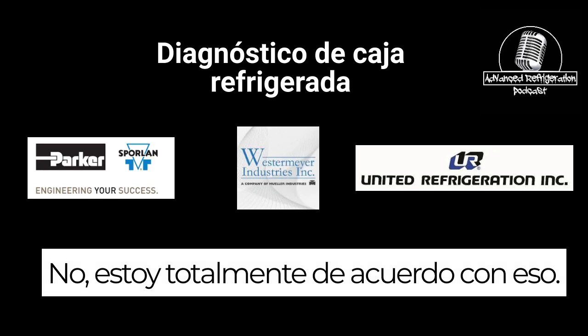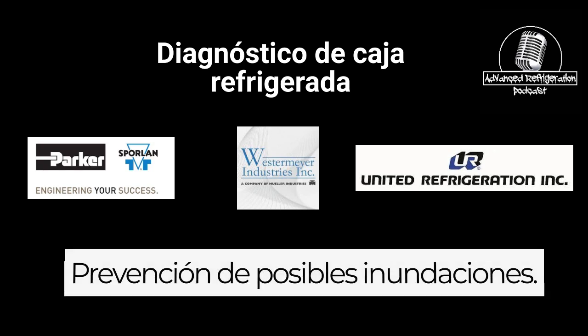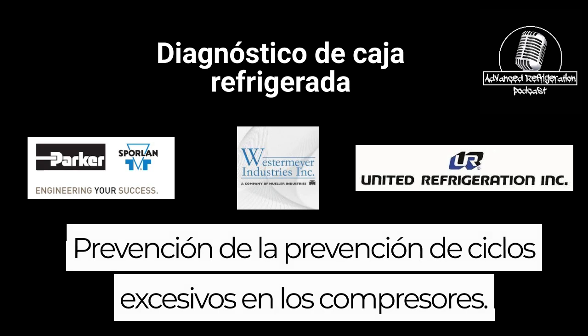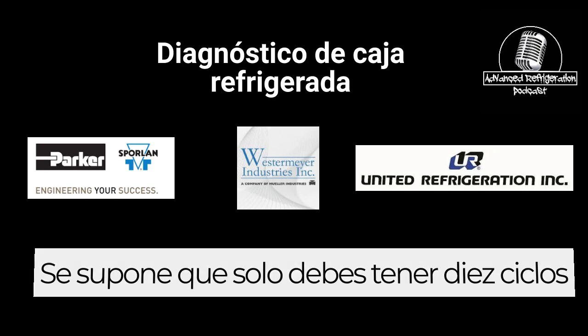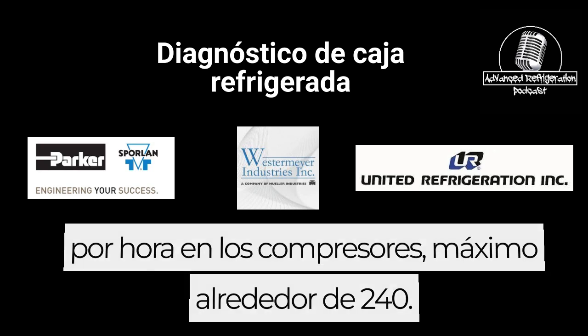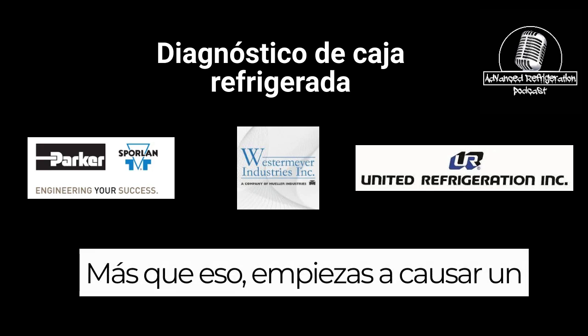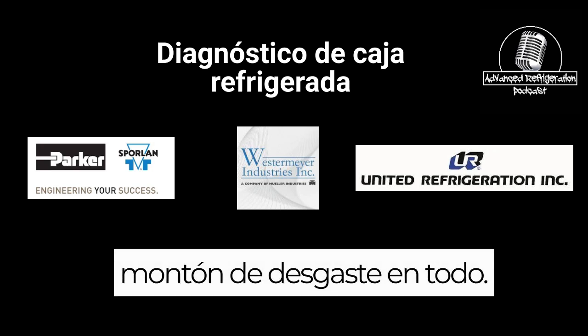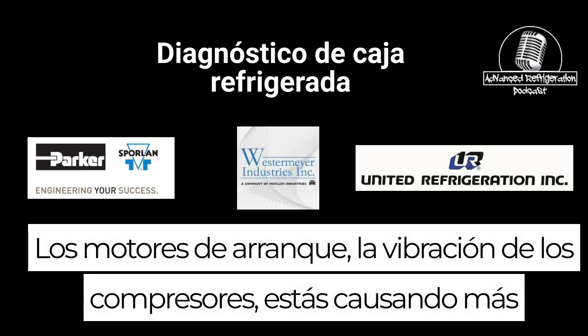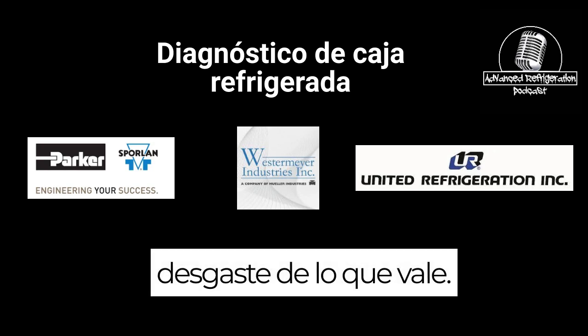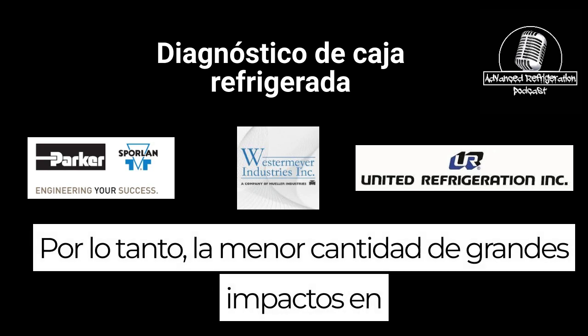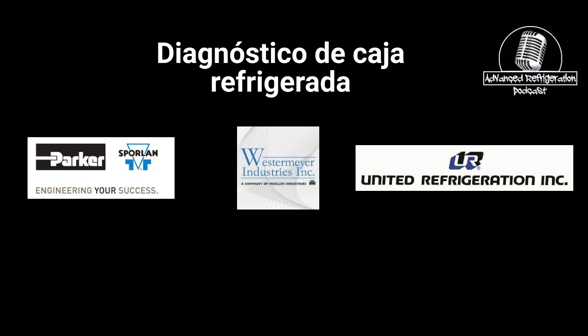No, I totally agree with it. Preventing potential flood back, preventing overcycling on the compressors. You're only really supposed to have 10 cycles per hour on the compressors, max about 240. Any more than that, you start causing a whole bunch of wear and tear on everything. The starters, the compressors, vibration. You're causing more wear and tear than what it's worth. So the less amount of big impacts on the rack that you can cause, the better.